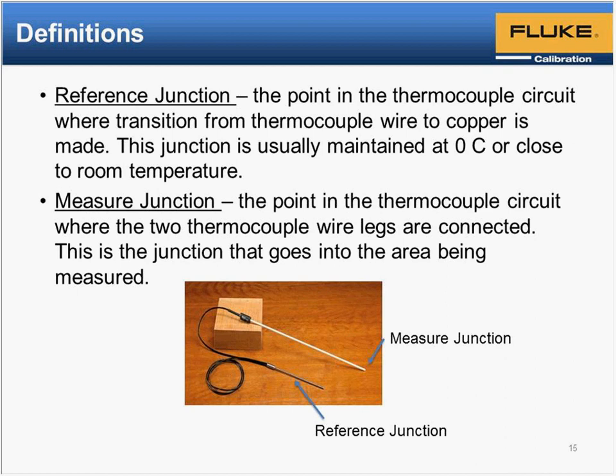Okay, yeah. So for the reference junction, when we solder the wire, the standard was a low temperature solder with lead. A few years ago, we had to stop using lead, so now we're using a little higher temperature solder, and it really isn't any standard. As a matter of fact, I've been at some laboratories where they still use mercury cups because they are convenient. You have a bit of mercury in the bottom of your tube, and you put the wires down, both touching the mercury, and that makes the circuit. So you don't have to worry about using silver solder or anything like that. Just use whatever standard you'd use for electronics.